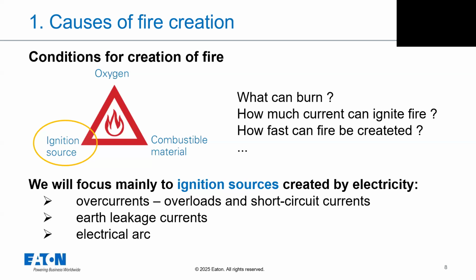Then more questions come: what can burn, how much current can start ignition of fire, and so on. Now we will focus mainly on sources which can create an arc, and it's good to have in mind a scale of importance. Overcurrent is usually something that's part of each design - overload and short circuit current protection. Then the next category of reasons for fires are earth leakage currents, and the last one, discussed more and more, is electrical arc, which can be the last ignition moment if all other conditions are fulfilled.